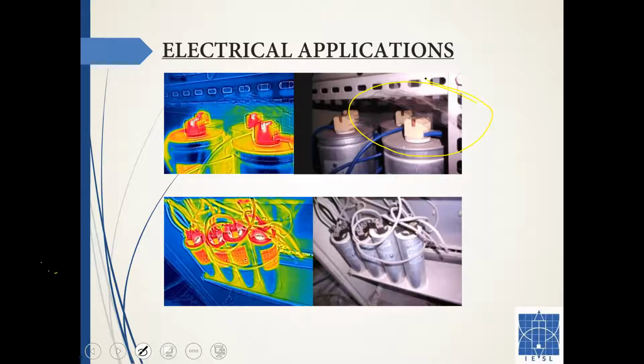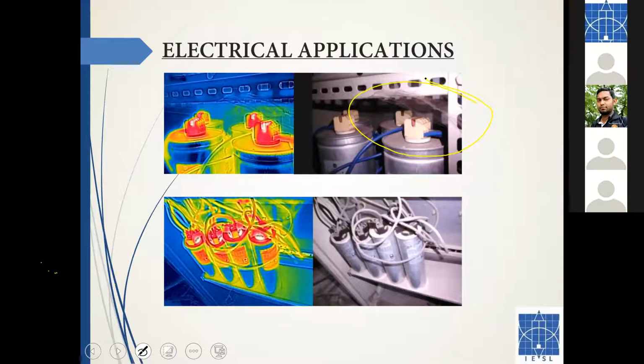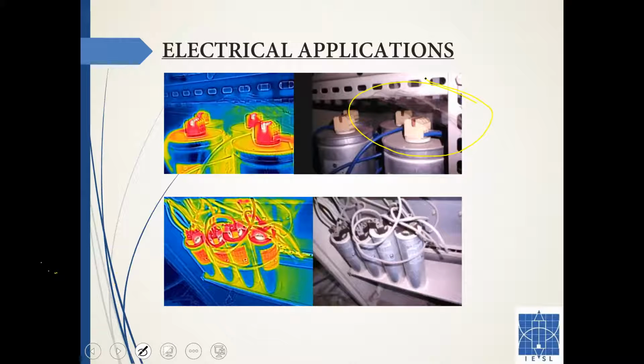Yeah, this is another classic example. Please excuse me for the focus of these images, but the thermal details are intact. So you can see here, there is a bad contact case going on. Here, it's really hot. So the recommendation obviously should be to replace this contactor, or at least inspect the contacts, right? Contactors can be really interesting to check, right? I have some images from dissected contactors, showing how bad the contact wear can be if the number of switching cycles is high on a given day. So you need to watch out for that, right?